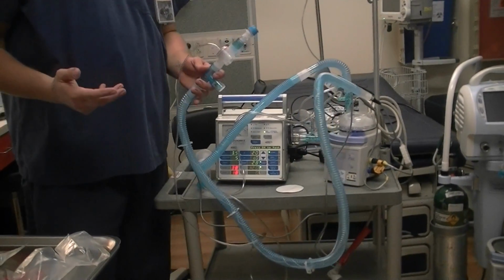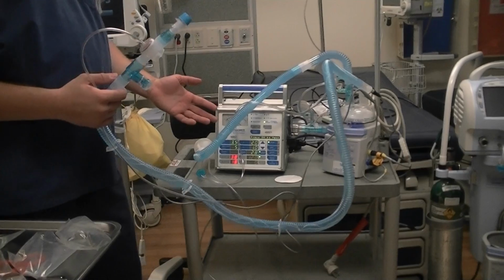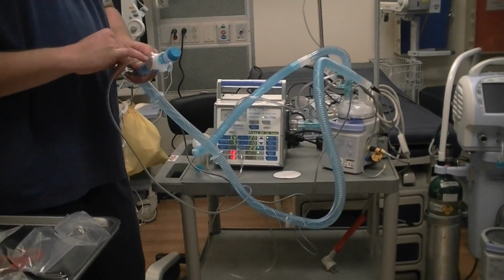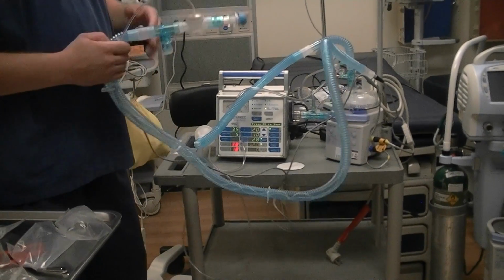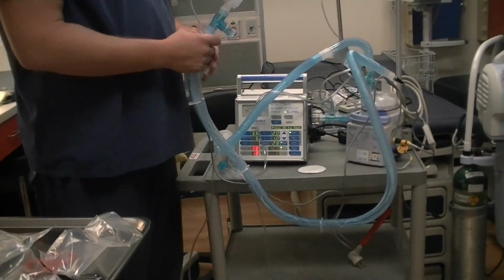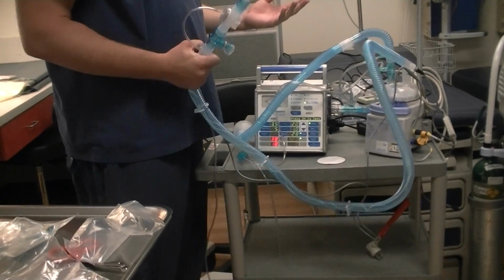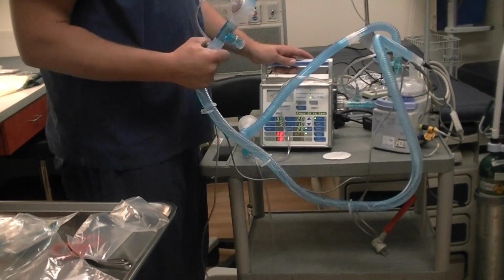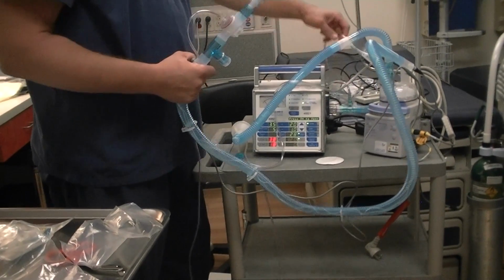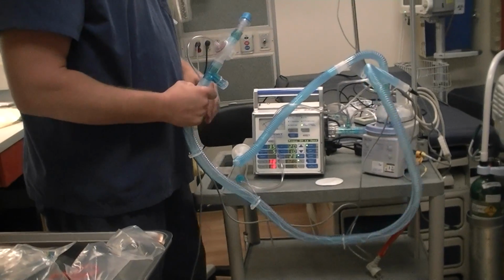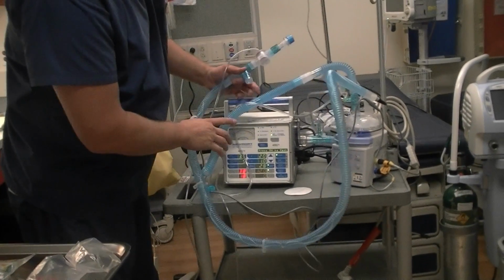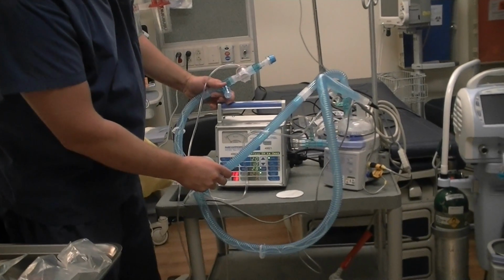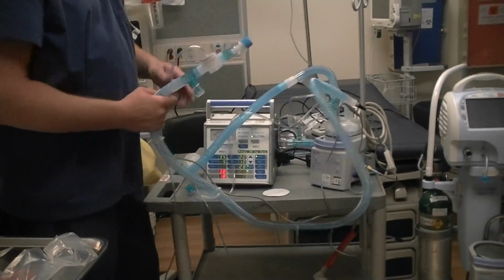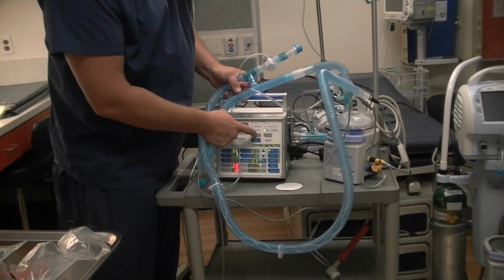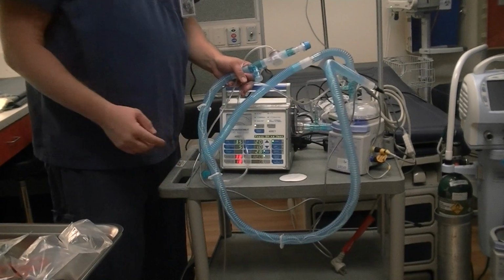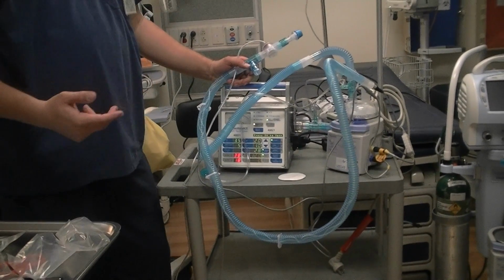If for any reason it did not pass cal, you most likely have a leak somewhere. Another issue could be a damaged exhalation line. But most common is a leak somewhere in the circuit. Recheck your circuit, retighten everything, anything that can cause a leak. You could clamp any lines off, such as your pressure line that goes to your green box alarm. You could clamp all those off. Another thing, if it were to fail, all you do is press the silence button and then press the manual inflation button again, and that will kick you right back into doing another cal.